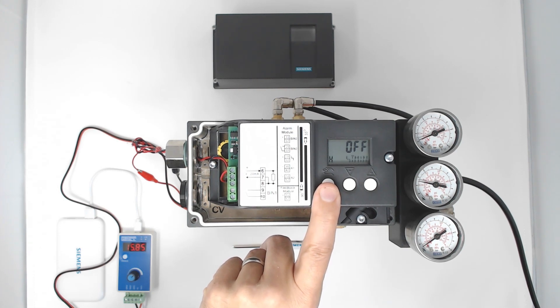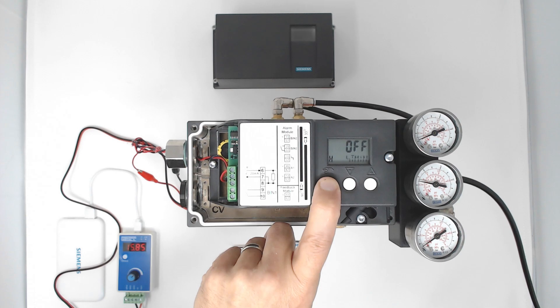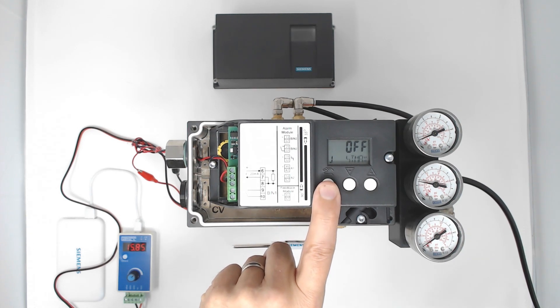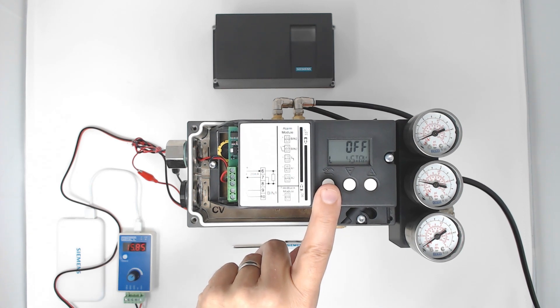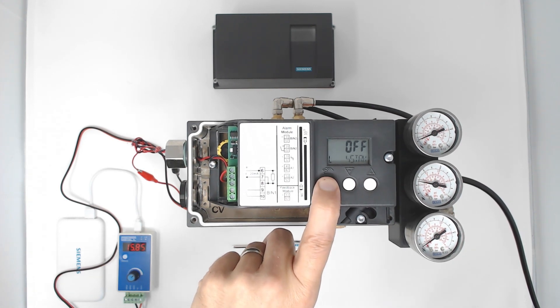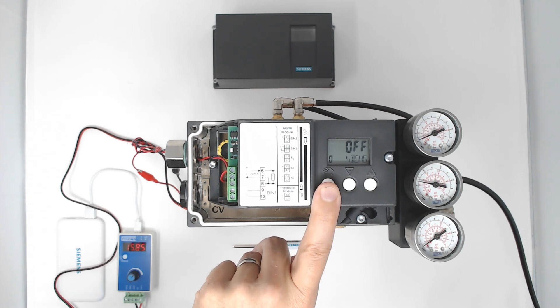The PS2 has a temperature sensor and it can trigger when that temperature reaches below a certain threshold or above a certain threshold. The number of valve strokes is detected, and you can have the PS2 indicate when a number of valve strokes has been reached. The same goes for changes of direction. These are good maintenance alarms to give you an indication of the wear and tear of the valve.